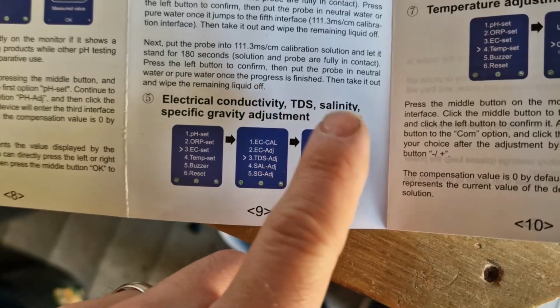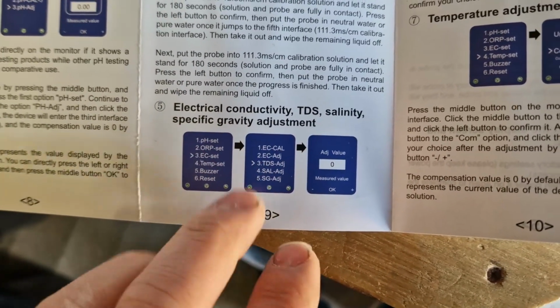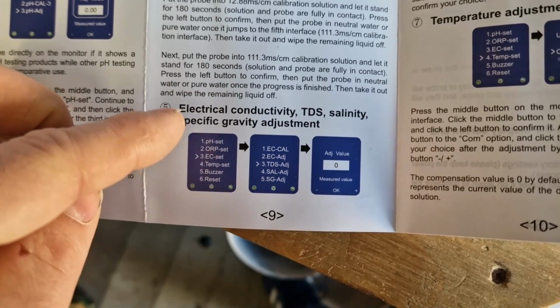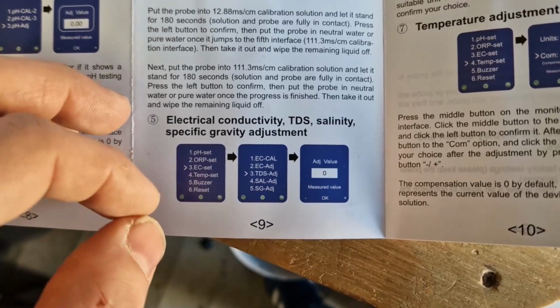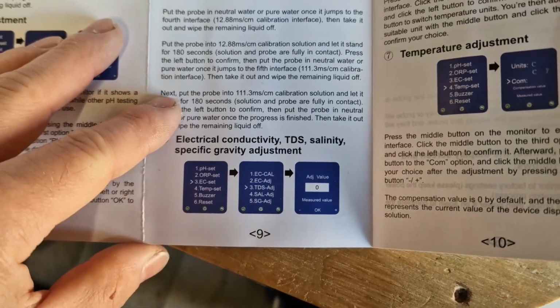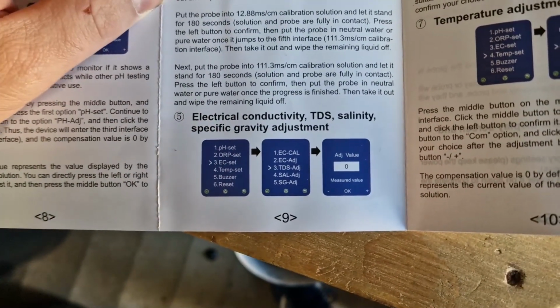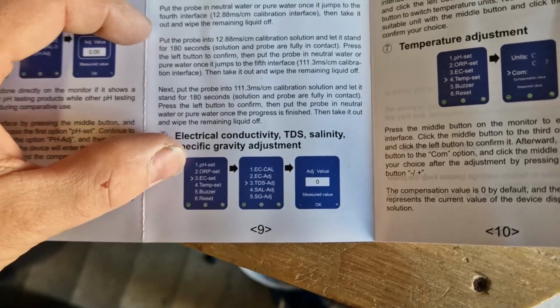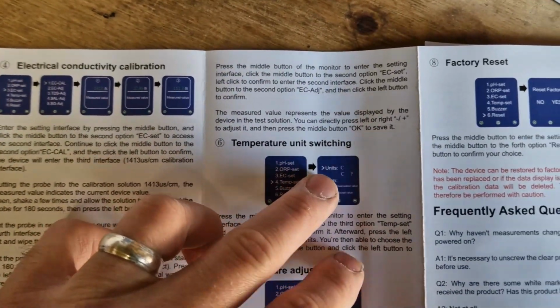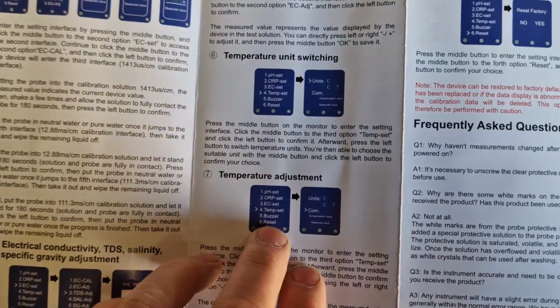So you've got these as well: TDS, salinity, specific gravity adjustment. So all these parameters you can alter within the monitor itself. If you feel as though it's not quite right, if you compare it to other monitors that you know are usually bang on, then you can adjust it within the monitor itself to suit what you think it should be. You can change the temperature unit from Celsius to Fahrenheit. So again, it's really adjustable, this. Just by going into the monitor itself, you can tell the monitor to change the unit to whatever you think it should be. So that's quite good.